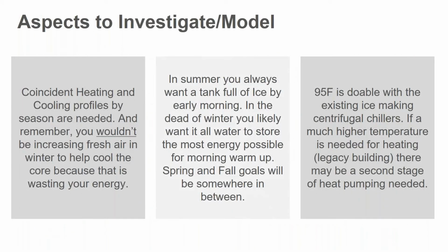So there's obviously things that you've got to look at. You've got to look at the coincident heating and cooling load profiles by season. You remember one thing that, in the wintertime, increasing fresh air used to help on the whole free cooling thing. You wouldn't want to do that now, okay? Because now that free cooling is wasting energy that you want to save for tomorrow. So you want to save that by melting ice. In the summer, you always want the tanks full of ice in the morning. And in the winter, in the morning, your goal is to have 100% water before you get into the heating. And so in the spring and fall, it's going to be somewhere in between those two extremes. But that's certainly something that needs to get looked at.